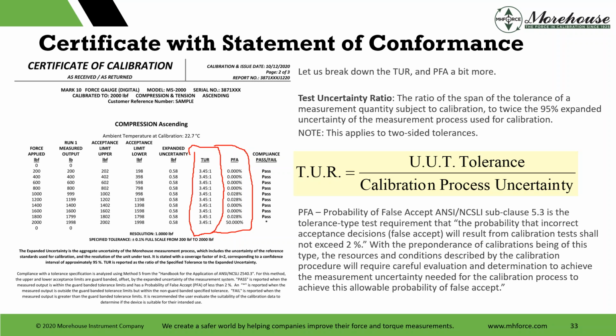Basically saying, hey, calculate this, and as you calculate the PFA, if anything is larger than 2%, you cannot make the conformance pass-fail or compliance pass-fail. You cannot make a statement of pass. You could make a statement of fail if it's above 2%, or you could choose to let the end user evaluate and see if it's okay or not okay.